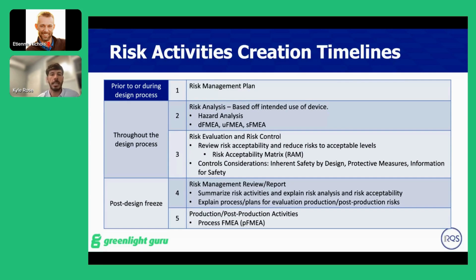All of these have key risk profiles that need to be captured and documented, and these will affect your design choices, right? So on what materials you can use, what testing you have to do, these have to be identified early in the process so you don't waste time, you don't skip steps, you don't have to go back and update some testing or things like that. So starting your hazard analysis and your risk management plan very, very early in the process is highly recommended for any type of device.